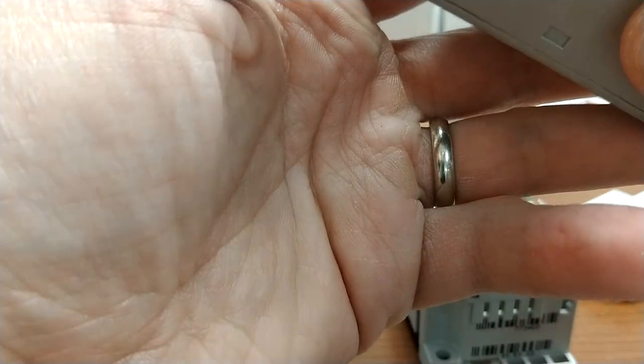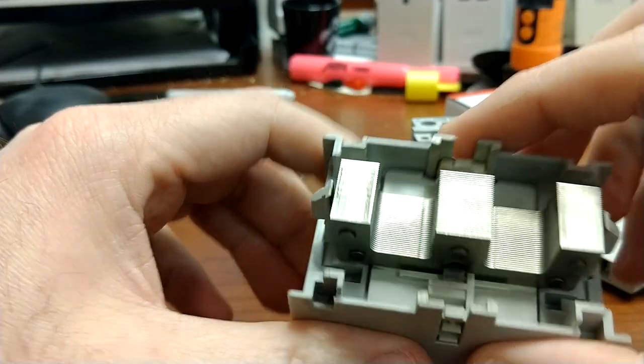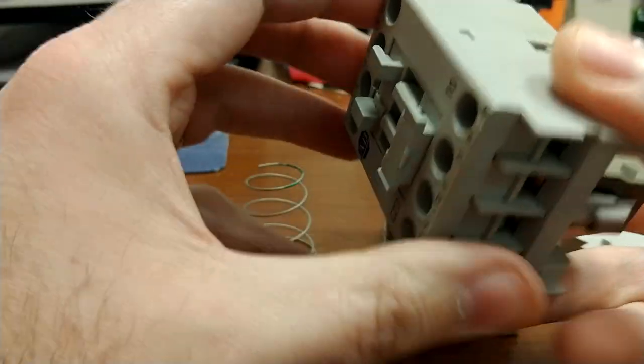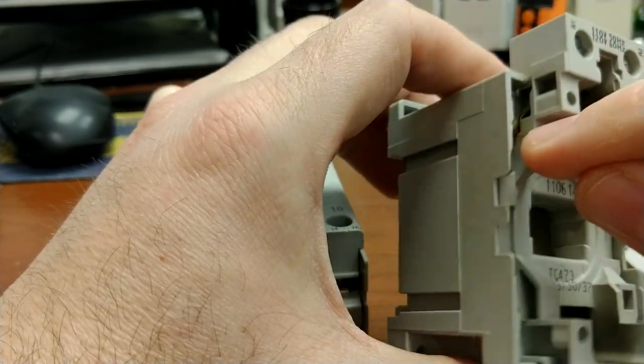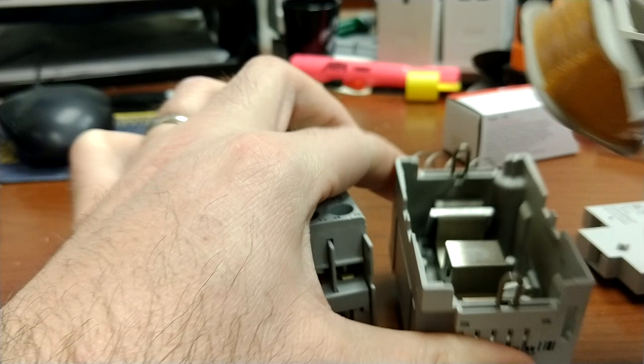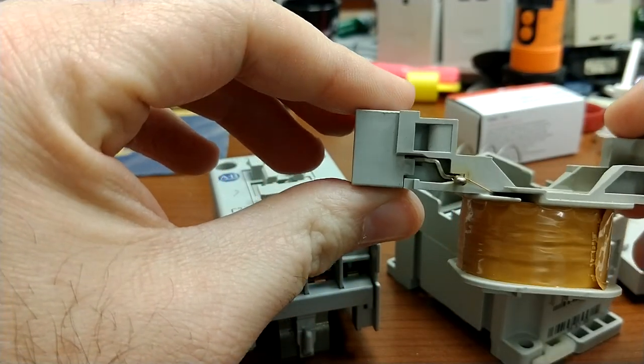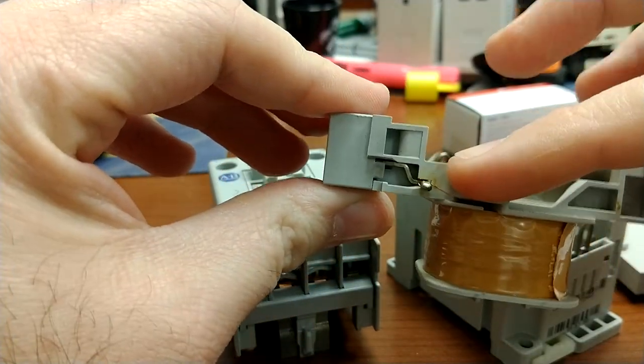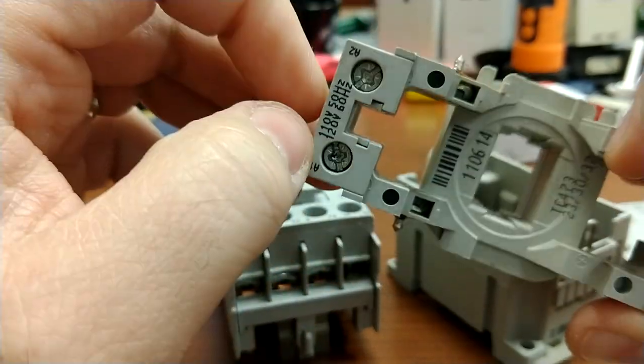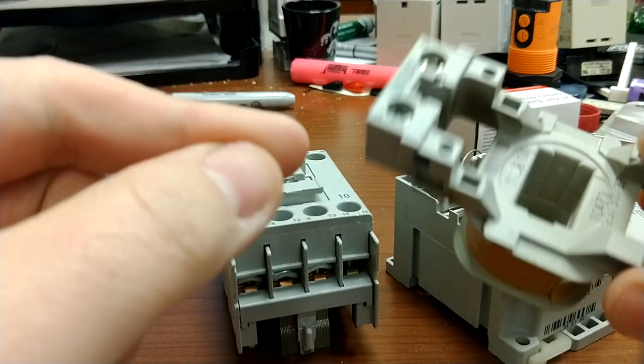Let's see, can I break this apart anymore? Where can I go? So, I'm taking a look, see if I can, sorry, you're looking at my hand. I'm seeing if I can break this apart more. But typically, they don't want you to get too much in there. But this is the electrical coil. And if you take a look, you'll see a small little wire, maybe right there. Pull this out. And you can see, this is my encapsulated coil. And you can see a small little wire right there. That's isolated to the A1 and a small little wire right there going out.